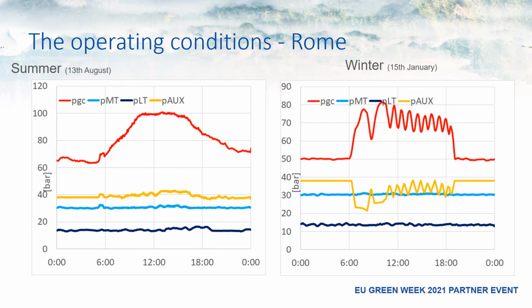This is an example of the operating conditions in Rome. We have a summer day on the left and a winter day on the right. You can see that the peculiarity of the Rome system is the fact that the air handling unit is operating only during the day, so when the supermarket is open. During the day, you can see in the summer on the left-hand side we have transcritical operations here in the central part of the day, while operations are subcritical in the night.